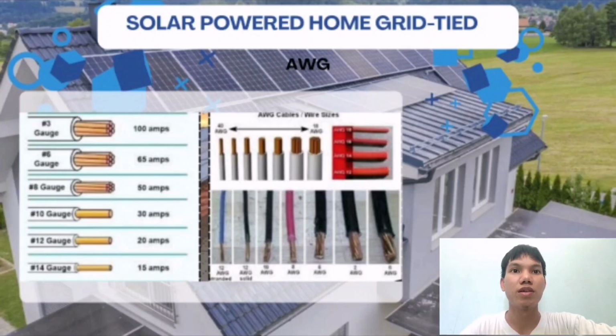The smaller the number, the larger the wire. As you move from a number 14 gauge up to a number 2 gauge, the physical thickness of the copper increases significantly, and with that thickness comes a higher capacity to carry current, measured in amperes. Every component we've discussed, from your solar panels to your battery inverter, operates at a specific amperage. If you try to push 100 amperes through a number 14 gauge wire rated for only 15 amperes, the wire will act like a heating element. It will become red hot, melt its insulation, and potentially cause a fire. This is why you use thicker wires, like the number 2 gauge shown in the chart.